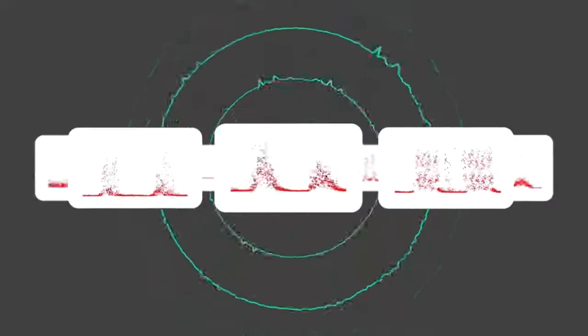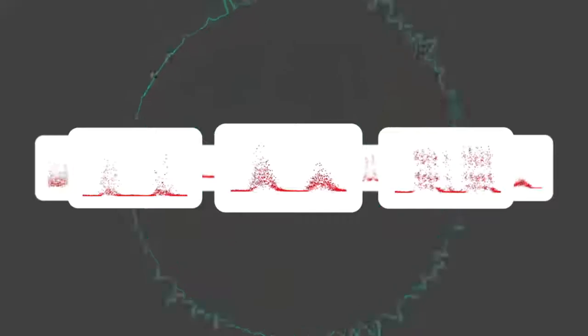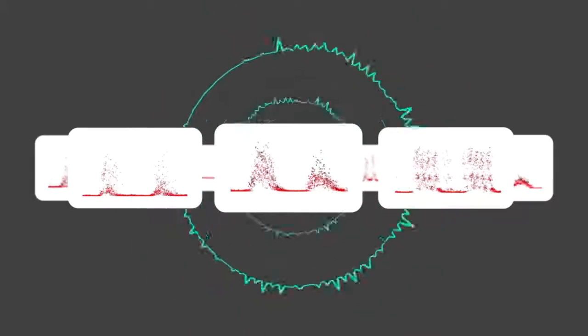To be able to decide on corrective actions, you need to know the type of the partial discharge. The discharge pattern displayed here is typical for a surface discharge.